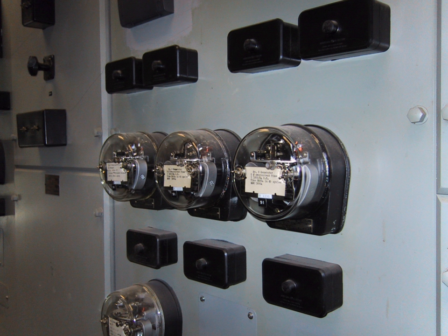Topic: Directional relay. A directional relay uses an additional polarizing source of voltage or current to determine the direction of a fault. Directional elements respond to the phase shift between a polarizing quantity and an operate quantity. The fault can be located upstream or downstream of the relay's location, allowing appropriate protective devices to be operated inside or outside of the zone of protection.